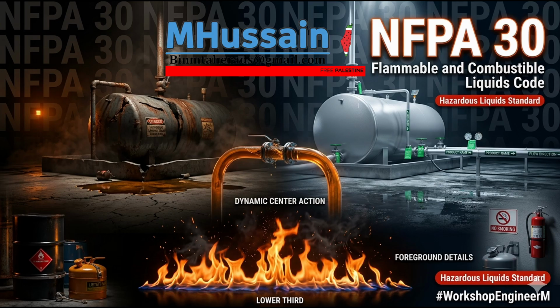Because ignitable vapors are almost universally heavier than air, right? They don't float up like steam. They behave exactly like water. They pour over the edges of a tank, they sink to the floor, and they pool in trenches, drains, and corners. And that's exactly what happened in India. This massive, invisible lake of highly explosive vapor just pooled in a stagnant pocket of the plant because the airflow was inadequate.